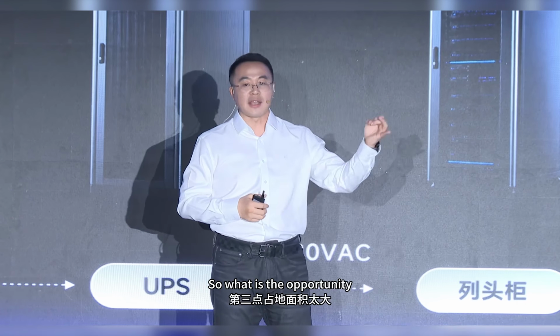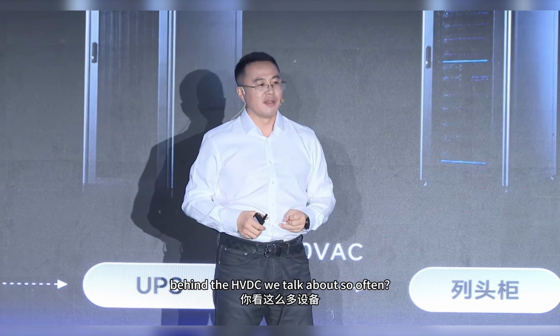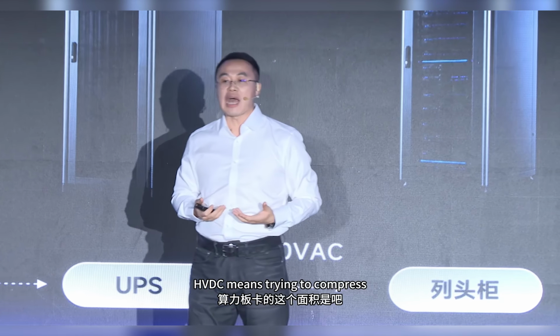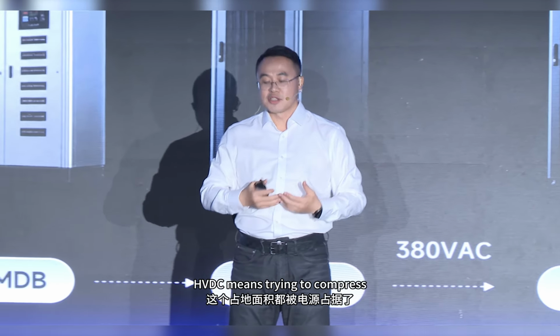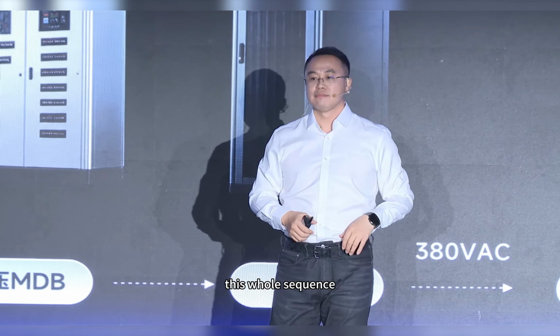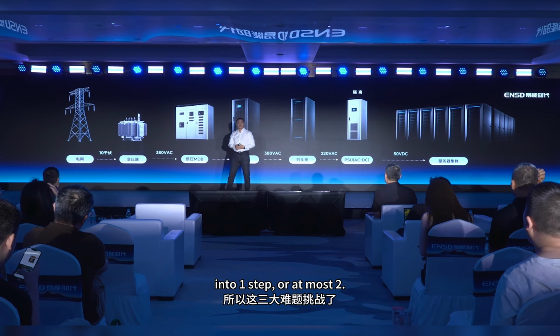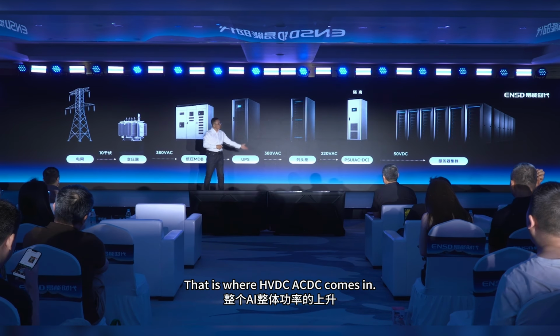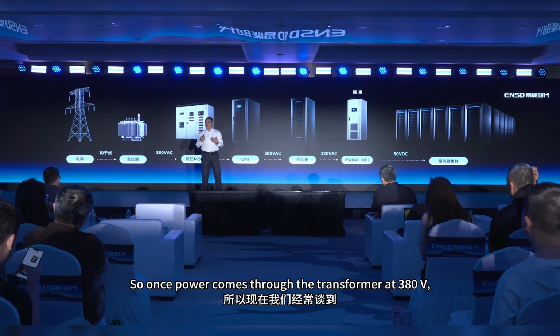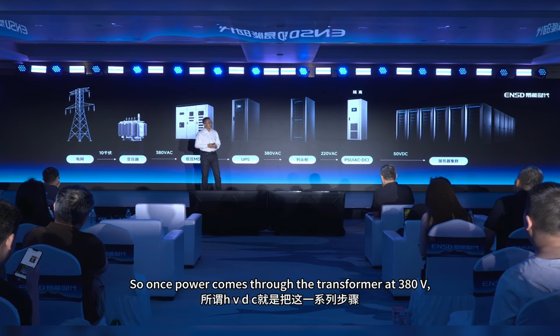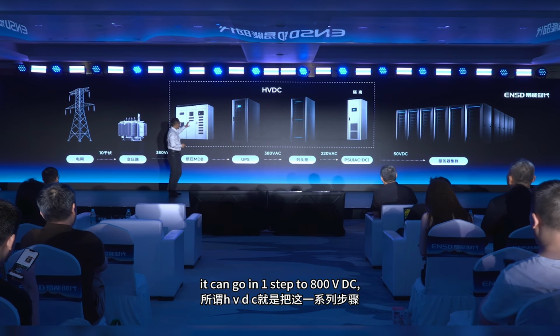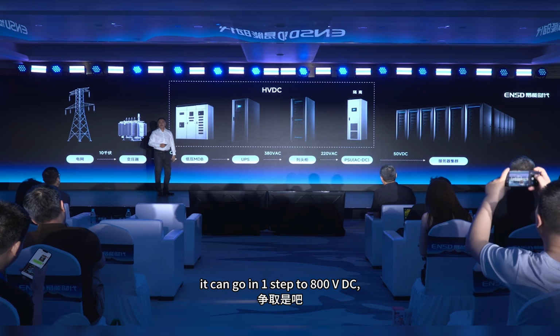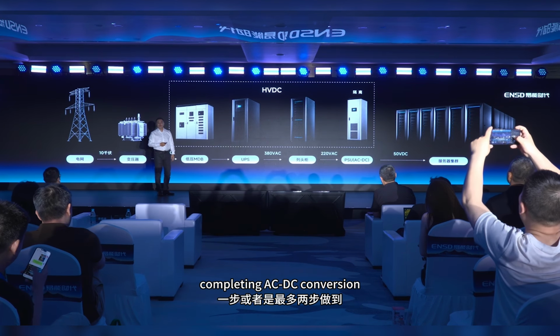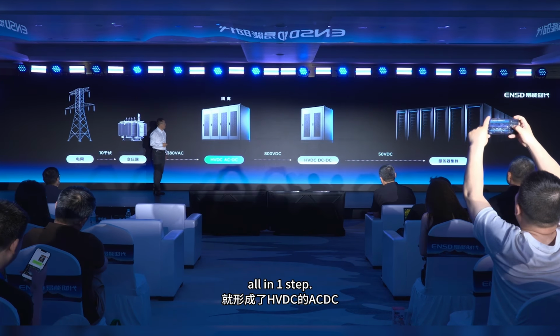So what is the opportunity behind the HVDC we talk about so often? HVDC means trying to compress this whole sequence into one step, or at most two. That is where HVDC AC-DC comes in. Once power comes through the transformer at 380 volts, it can go in one step to 800 volts DC, completing AC-DC conversion and isolation right there, all in one step.